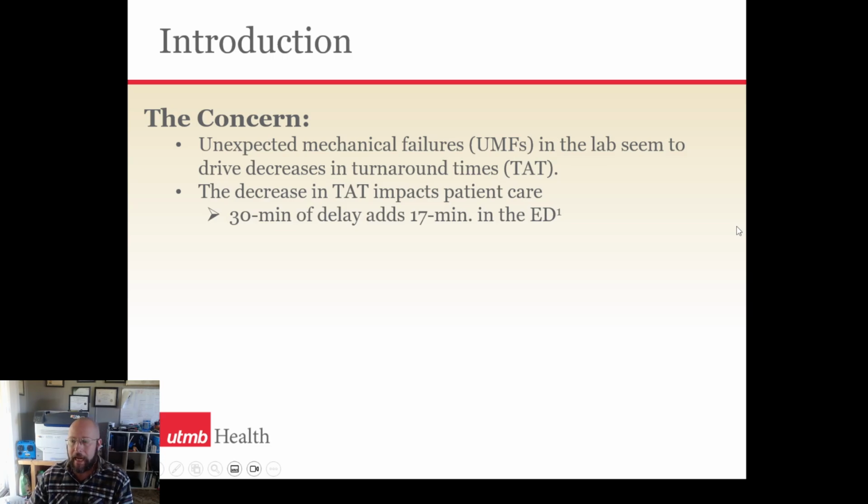So the concern that I was really focused on was unexpected mechanical failures. Let me give you a little bit of background on this. In one of the rural laboratories that I worked in, in fact the one that I oversee today, we had a chemistry platform that was having some issues, and I believe it was with ferritin results. So we were calibrating ferritins. We kept getting absurd results on our ferritins, and that resulted in them calling me in to ask if I could continually troubleshoot this instrument.